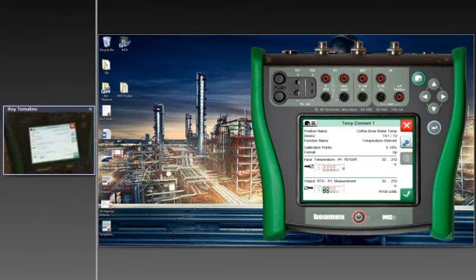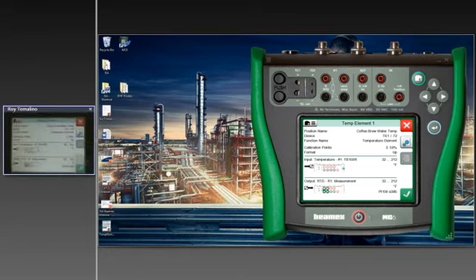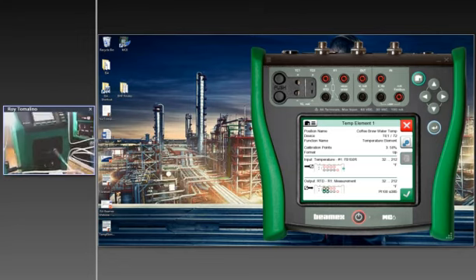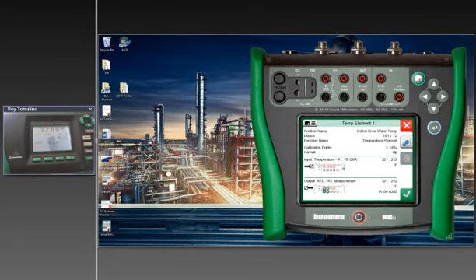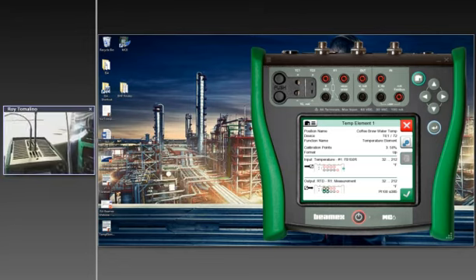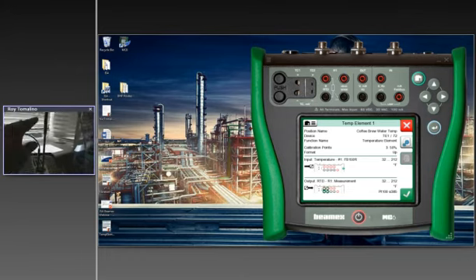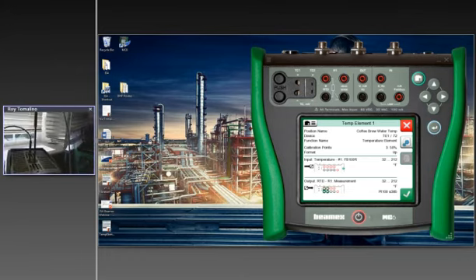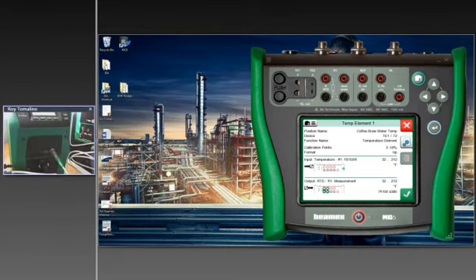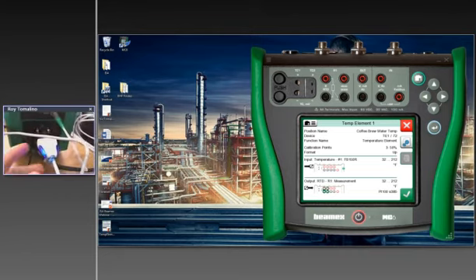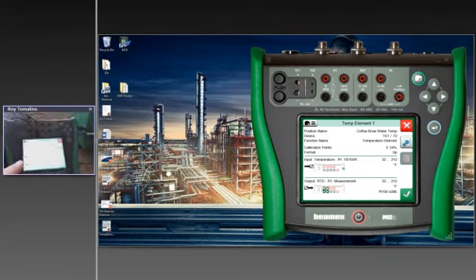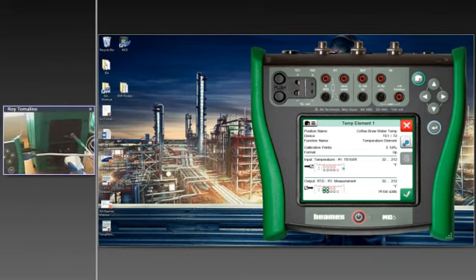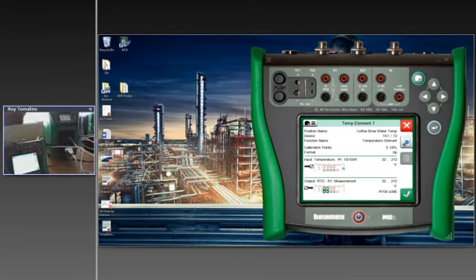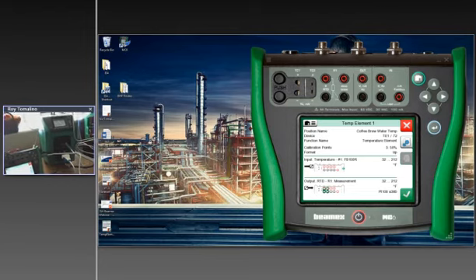I've got my MC6 calibrator, and it's set up to do a test here, and I'll show you this on the screen. Next to it, I've got my temperature source. On top, I have my temperature element under test. That's the one on the left. Then I have a PRT, a reference probe, on the right to make the dry block more accurate. And I've got this all connected through a cable going over to the MC6. So the calibrator is controlling the dry block, telling it what temperature to hit, and grabbing the temperature values at each step in order to do the calculation.